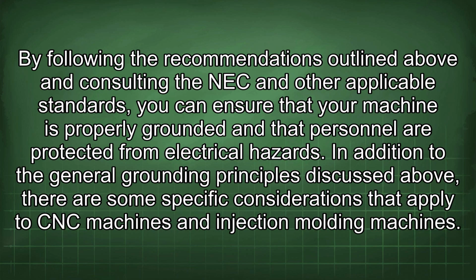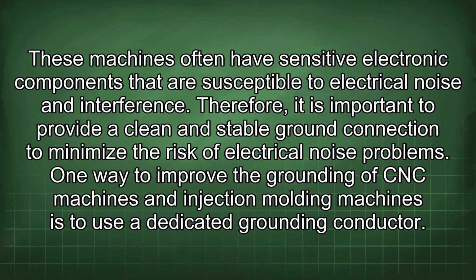By following the recommendations outlined above and consulting the NEC and other applicable standards, you can ensure that your machine is properly grounded and that personnel are protected from electrical hazards. In addition to the general grounding principles discussed above, there are some specific considerations that apply to CNC machines and injection molding machines. These machines often have sensitive electronic components that are susceptible to electrical noise and interference. Therefore, it is important to provide a clean and stable ground connection to minimize the risk of electrical noise problems.